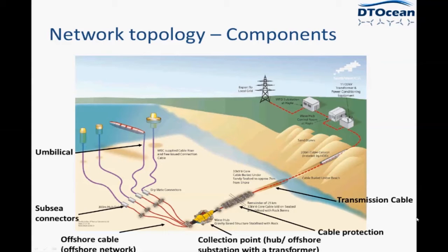One of the things we focused on a lot is the seabed conditions and the installation of the cable. So the shortest path, which would give us the shortest distance of cable, which would give us the cheapest cost, may not give us the most low-cost installation method, depending on the type of seabed conditions. So what we need to try and work out is how we can include going around a certain seabed condition if it helps minimise the overall cost. And that's a very crucial thing, I think, to return the overall lowest cost.